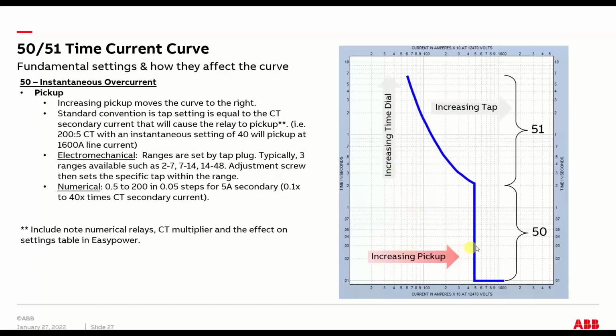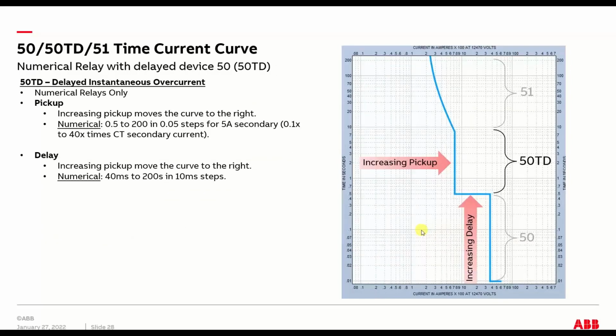Your 50 is then this part of the curve down here, and that typically only has a pickup value. It may have a range, the set plus the pickup value, but as you have an increasing pickup, that moves this part of the curve to the left or the right in terms of amps. And all this stuff carries forward into the numerical relay.